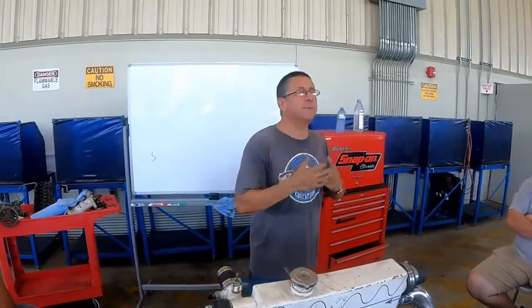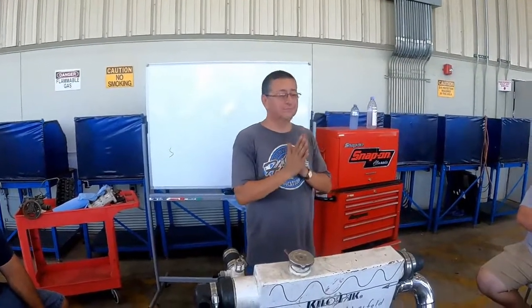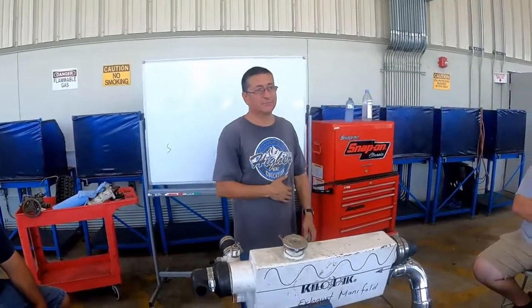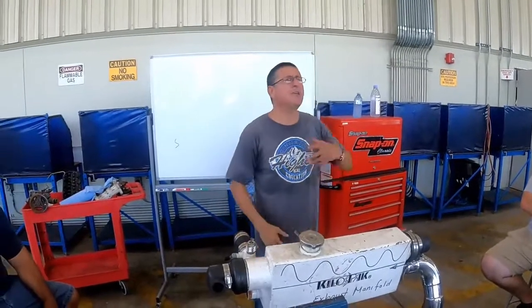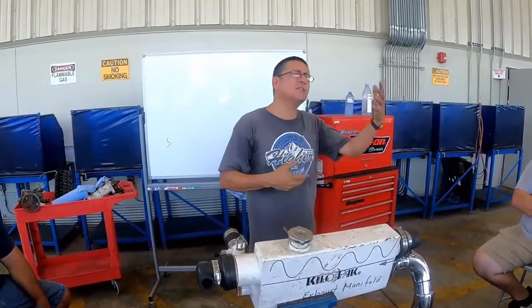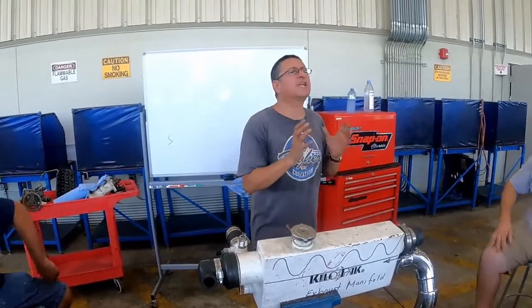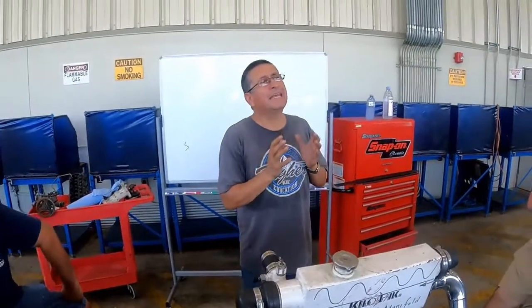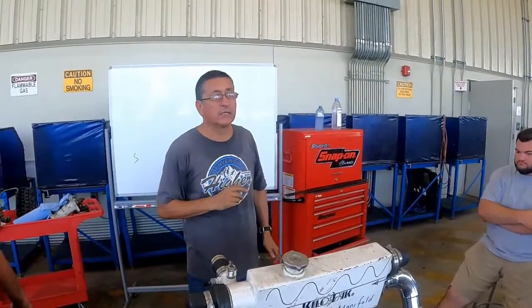For that reason, Roberto, when you receive a phone call related to temperature, you need to analyze the situation. Ask the customer a million questions. What is the color of the smoke? How is the temperature? Is it at high speed? Is it at low? In order to identify if the problem is on the coolant side or on the raw water side. Probably the problem is on the raw water side and it's easy to solve. If the problem is on the coolant side, you have more elements to check.